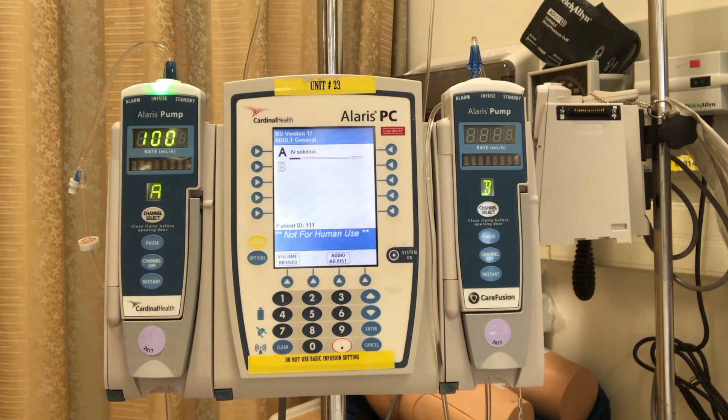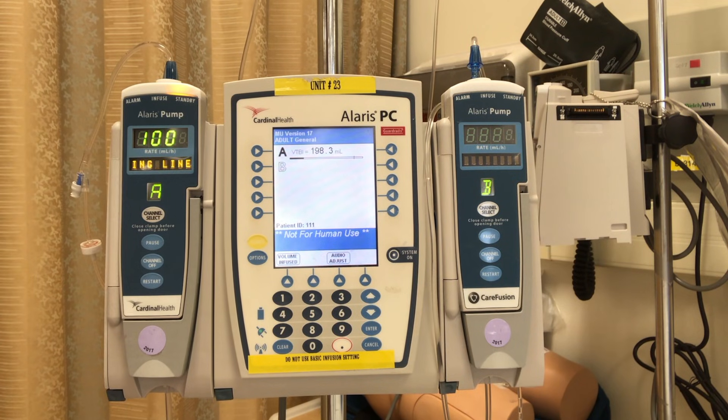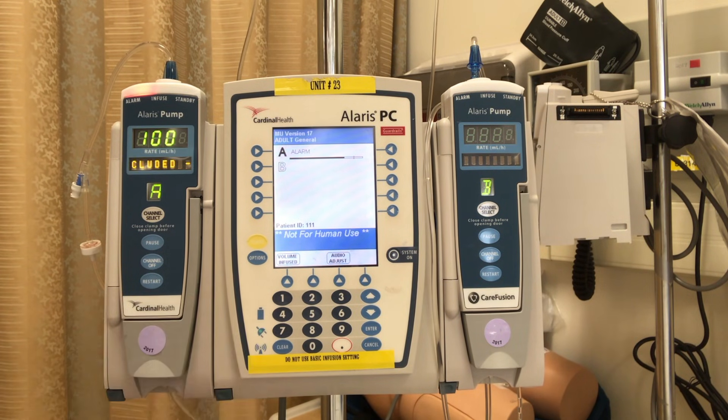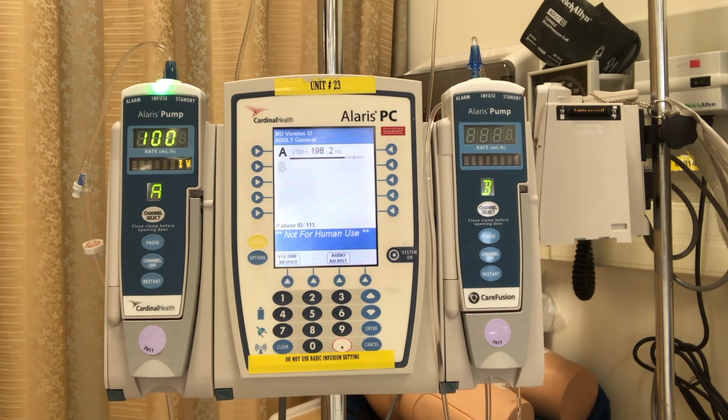The next troubleshooting we're going to look at is when there's a problem downstream of the chamber. You'll see it's checking the line — that's because I've occluded the roller clamp to demonstrate this. It's gone to yellow while the machine checks the line to find the source of the problem. It will soon tell me that it is occluded on the patient's side. This is an indicator that I need to look at the line from the machine to the patient — and what I'm going to find is my clamp. I forgot to unroll it. Happens all the time. I'm going to unroll that, select my channel, and start my infusion. Wait a few seconds to make sure everything is fine before you turn your back — because if you don't, three steps away it's going to be beeping at you.